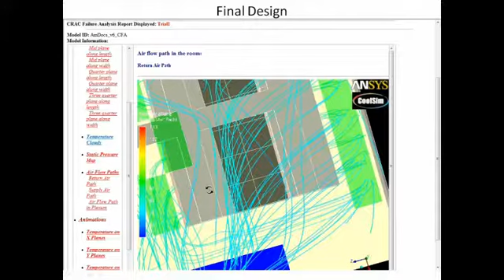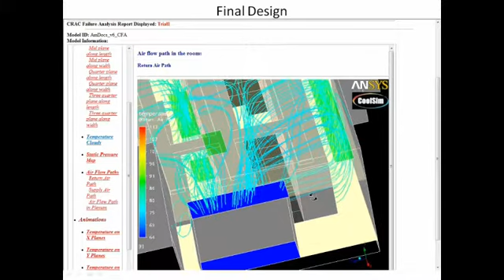So see right here, we can see there's no wrap around the ends. This is often what we see, where it wraps right around the end here. Right, because the curtains went up to the ceiling on the ends, but not above the racks themselves, so there was that option for the air to circle around, but it did not.